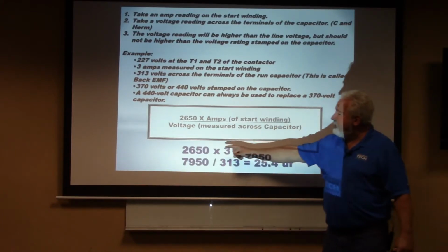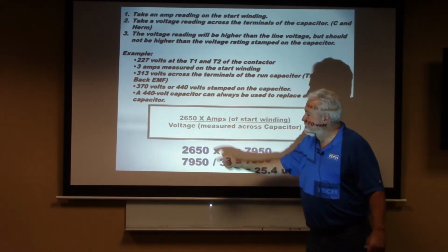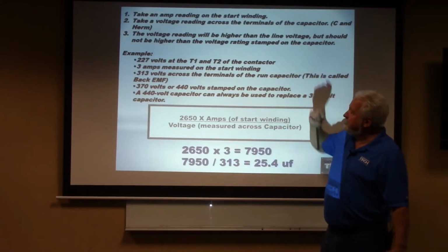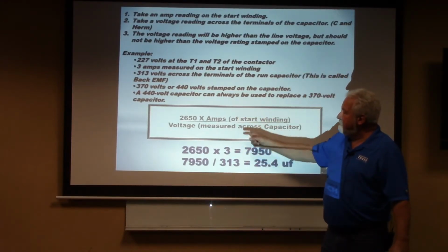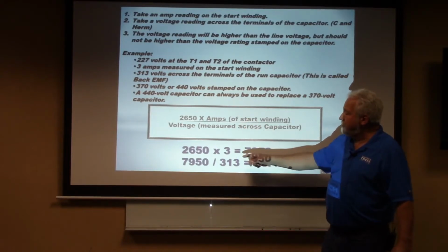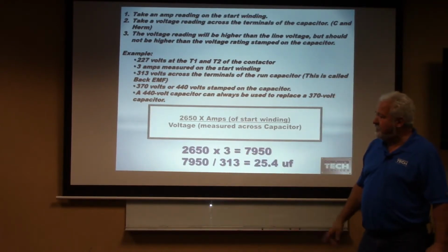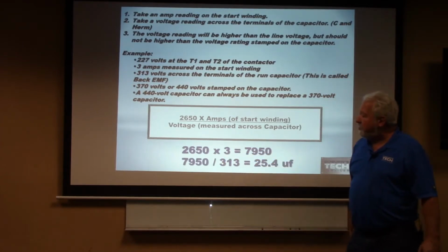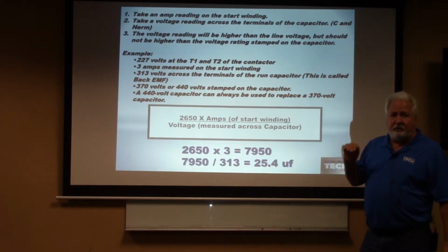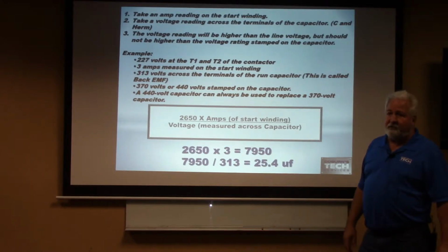So we take the 2650, that's a constant, it doesn't change, times my amperage of that start winding, divided by that voltage that I measured across there. So 2650 times 3 is 7950. 7950 divided by my 313, I'm operating right now while that unit is running 25.4 microfarad. If it's a 25 microfarad capacitor plus or minus 10%, how am I doing? If it's a 30 microfarad capacitor, how am I doing? Okay. Does that make sense? Good. But it's math. Nobody likes math.